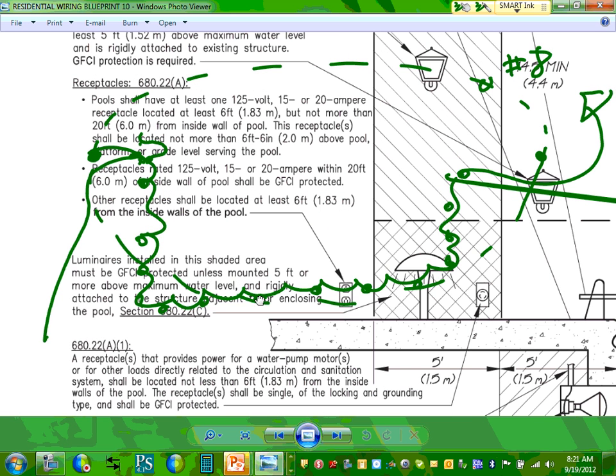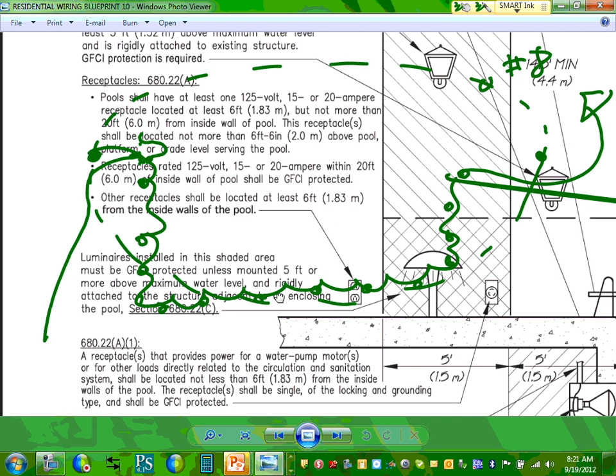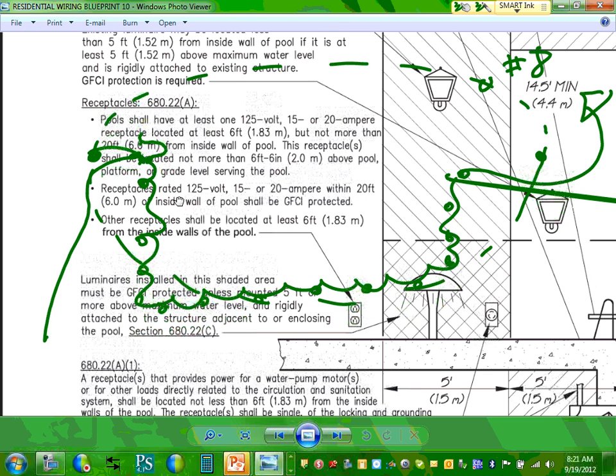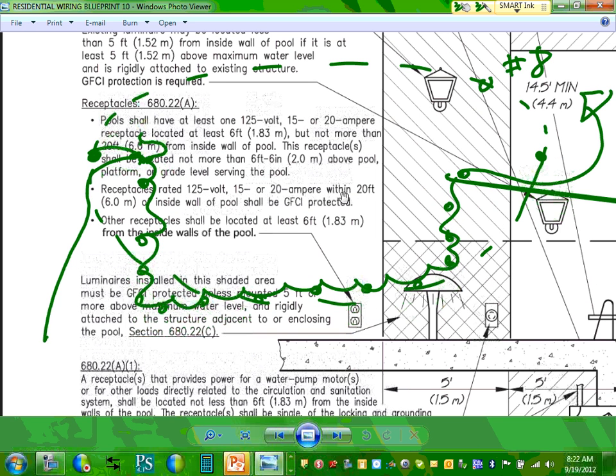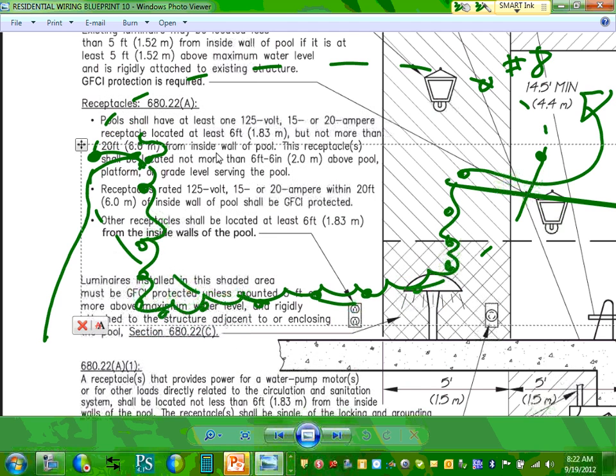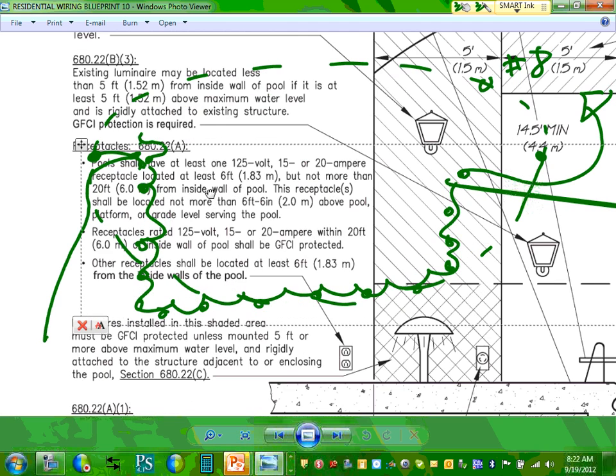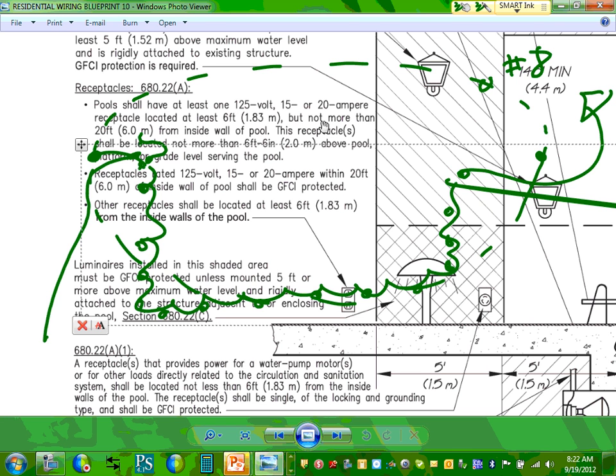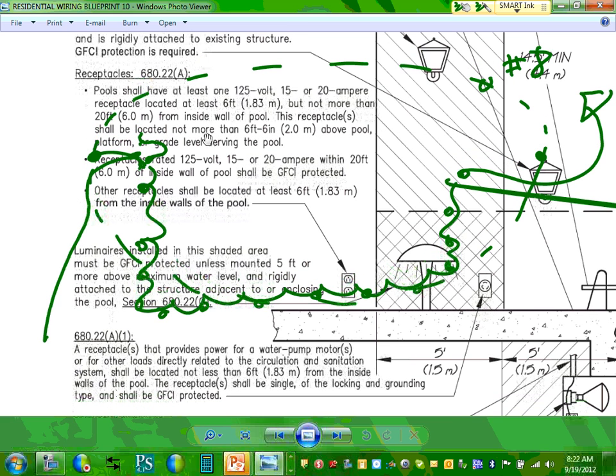Here's my receptacle. Did it say the receptacle shall be located at least 6 feet from the inside wall of the pool? Receptacles, I can't recall. Shall not be more than 6 feet 6 inches, 2 meters, above the pool platform. Other receptacles shall be located at least 6 feet from the inside. We're looking here. Receptacles within 20 feet of the wall. Right there, the first one. Okay, the pool shall have at least 6 feet, but not more than 20 feet, and located not more than 6 feet above the platform.